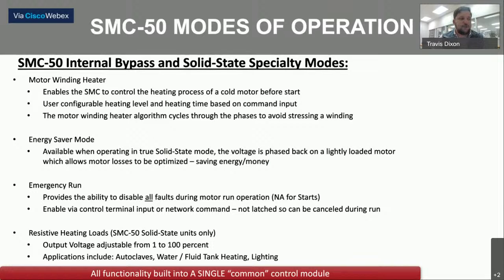The energy saver mode uses 2 power monitoring parameters to detect when the motor is lightly loaded, and it phases back the motor terminal voltage to save energy. Emergency run is if you want to disable all faults and just run it. It's really great for critical applications where continued operation of the process is the most important issue. The resistive heating is for solid state units only. It allows linear control of output voltage from 1 to 100% for loads like an autoclave, a fluid bath, some types of lighting, resistive loads.